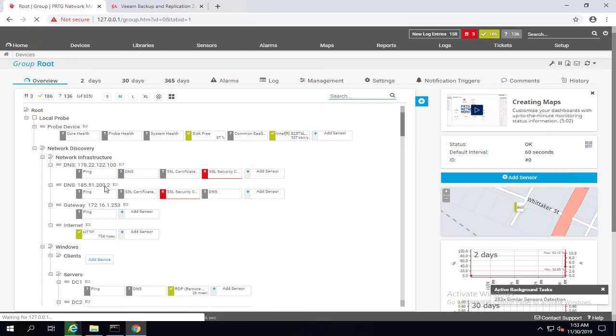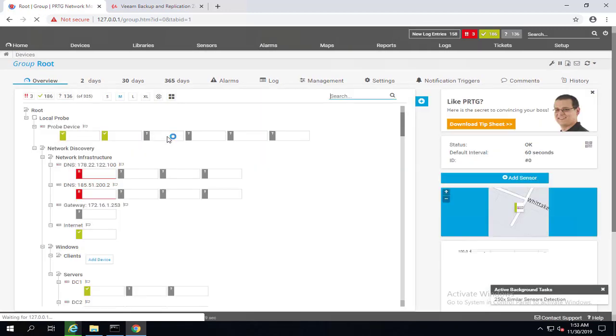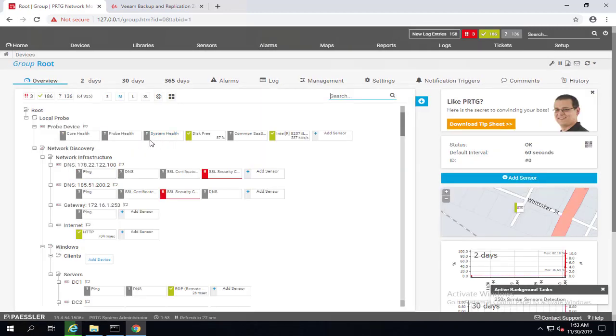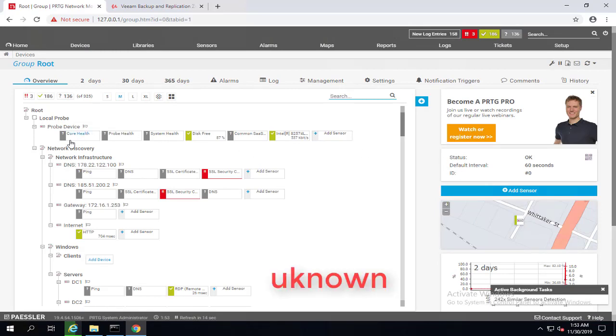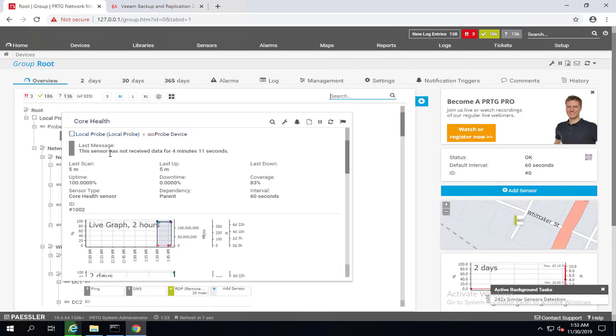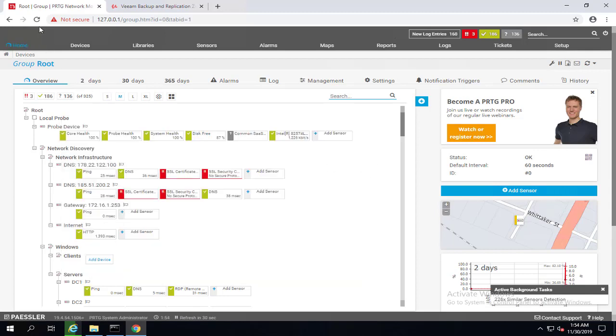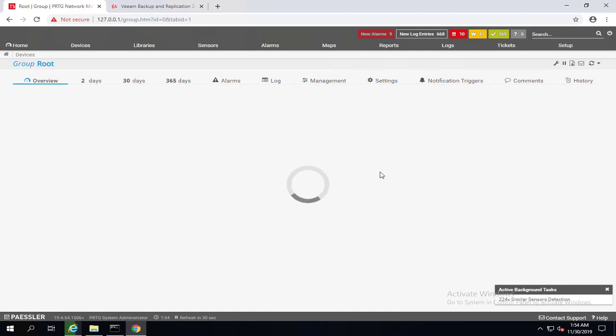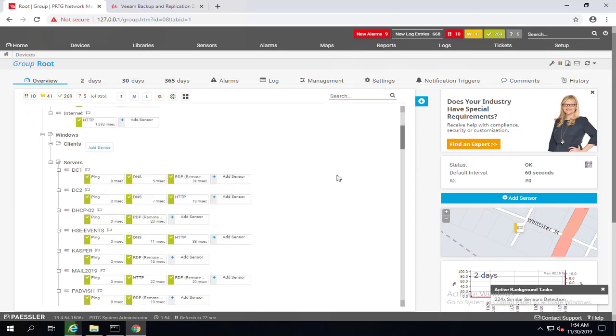We'll do a refresh for these sensors to initiate this sensor again. Sometimes when you switch to SSL like we did before here, some of the sensors are going to be with question mark. That means this sensor has not received data for, imagine, four minutes or whatever. Most of the time, it needs a few seconds for those sensors to be back again. Otherwise, you should restart your PRTG service on your administrative tools. It takes time to get back the sensors.